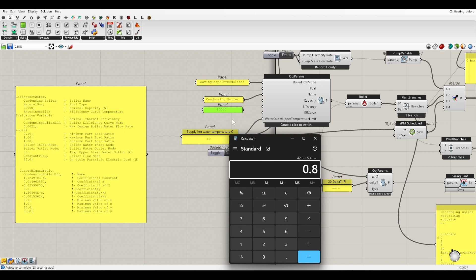Okay. Now let me close and turn off the simulation. For the boiler itself, it's using natural gas. The name we can say condensing boiler. The fuel is natural gas, so it's already natural gas. For capacity, we can hard size it. Nominal capacity, I don't know if it's enough, because previously at the peak hour it needs at least 43 kilowatt, and this one is 25 kilowatt. So for capacity, we're just using autosize. We're not going to hard size this one.